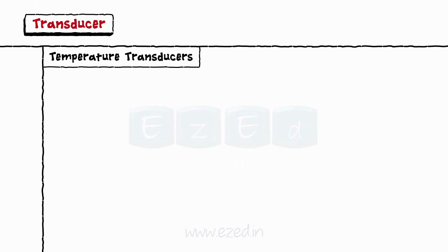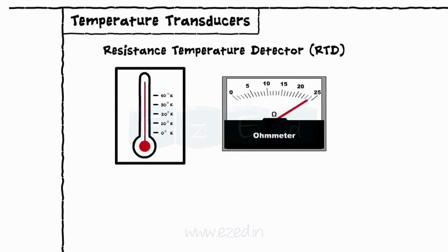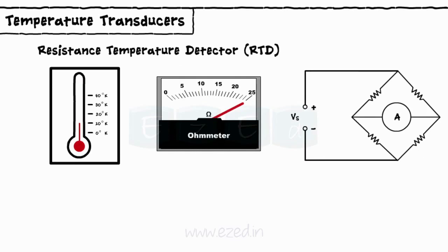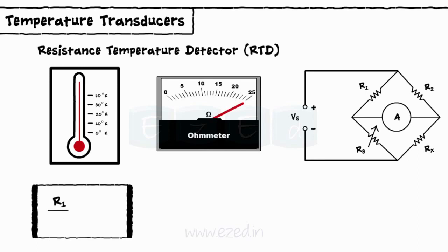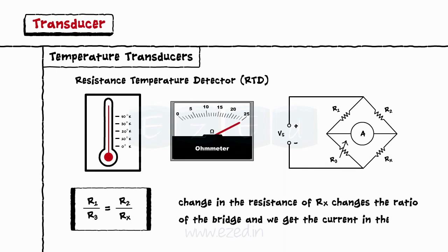The next temperature transducer is a resistance temperature detector or RTD. RTD is a sensor whose resistance changes with temperature. As we can see in the circuit, resistances R1 and R2 are fixed, R3 is variable, and Rx is the RTD. The ratio of the bridge becomes R1 upon R3 equals R2 upon Rx. Thus, a change in the resistance of Rx changes the ratio of the bridge and we get the current in the circuit.